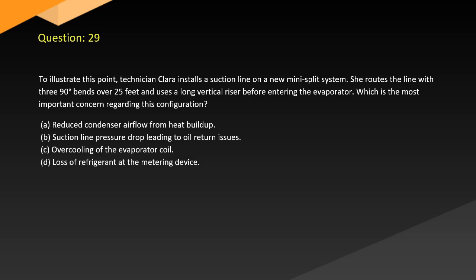Question 29. To illustrate this point, technician Clara installs a suction line on a new mini-split system. She routes the line with three 90-degree bends over 25 feet and uses a long vertical riser before entering the evaporator. Which is the most important concern regarding this configuration? A. Reduced condenser airflow from heat buildup. B. Suction line pressure drop leading to oil return issues. C. Overcooling of the evaporator coil. D. Loss of refrigerant at the metering device.